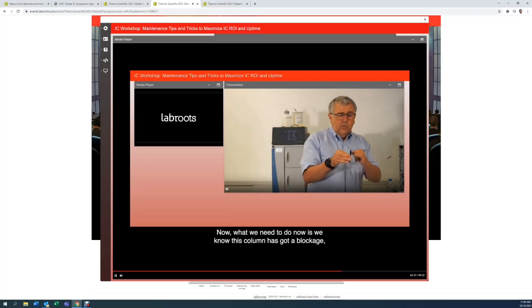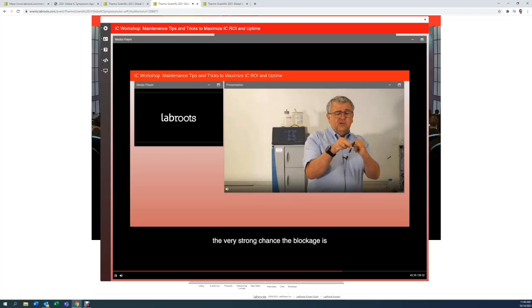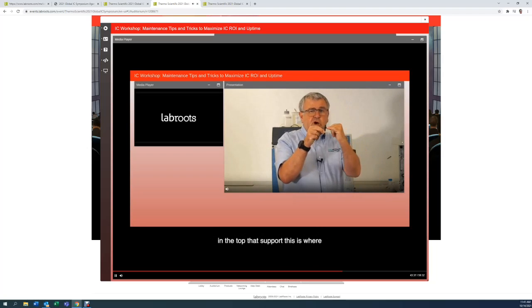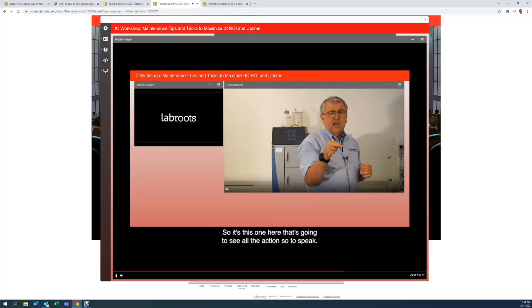Now, what we need to do now is we know this column has got a blockage. The very, very strong chance the blockage is in the top bed support. This is where the sample and the eluent hits first. This is where it will block. If it gets through this one, it'll get through that one. So it's this one here that's going to see all the action, so to speak.